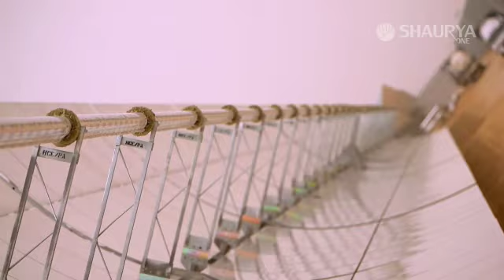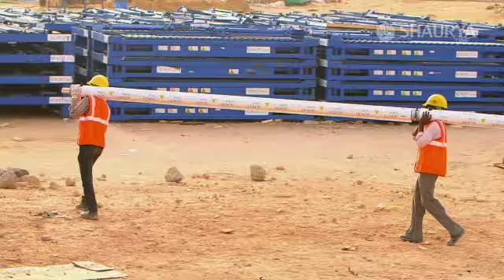Central to these operations is another expensive and complex piece of technology: the receiver tubes. These tubes are designed to trap the maximum amount of heat reflected by the mirrors. This is the high-end product that actually absorbs the radiation coming in from the sun, reflected from the mirror into this tube. It has a property like a steel tube through which the HTF is circulated. Their construction involves the extremely difficult feat of welding glass with metal.